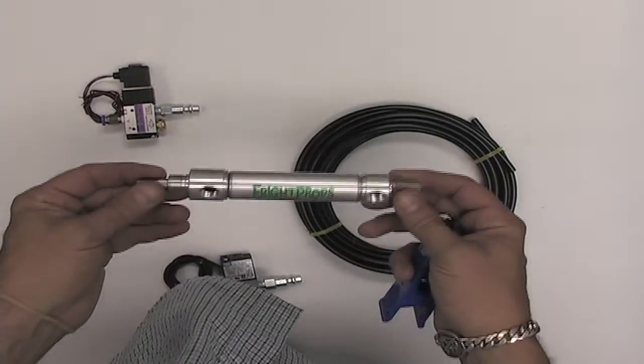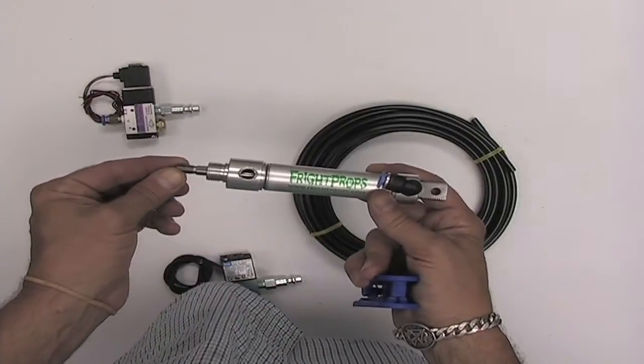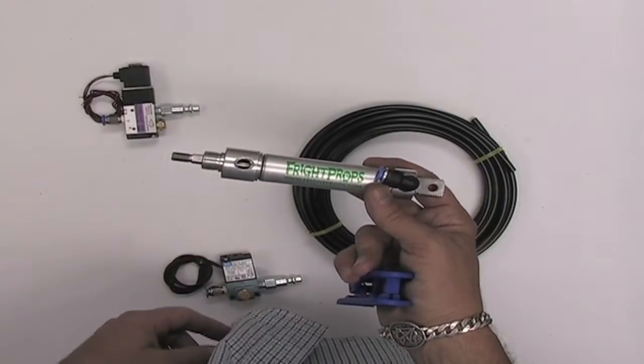You can also use a three-way solenoid with a double-acting cylinder. In this case, you're just going to push air to one side of the cylinder, say the bottom, and air will push it out, and the weight of your object is responsible for pushing it back in.